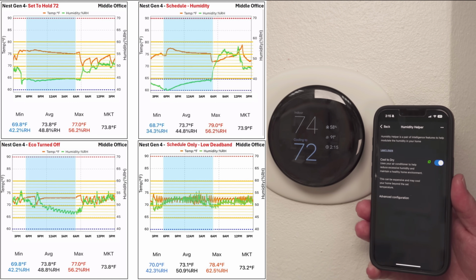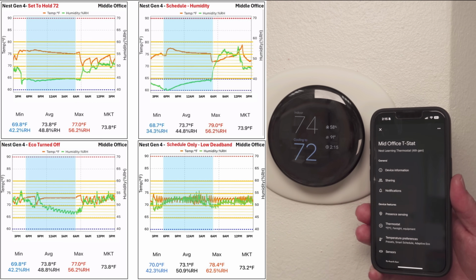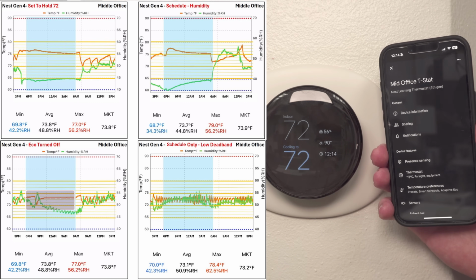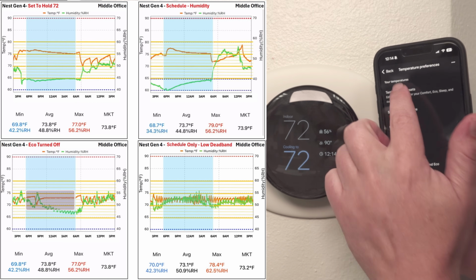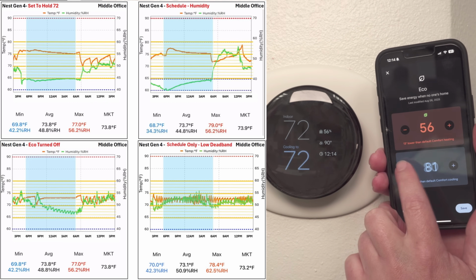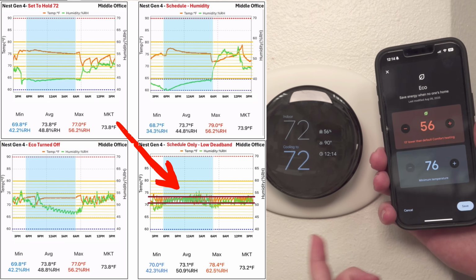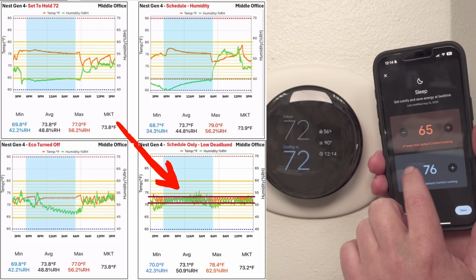Since this is the middle office and it only has one exterior wall, it has the smallest heat load of all three zones, which is partially why we don't see it cycling much at night. To fix this, I changed the temperature swing settings to 2 degrees, and now it runs all night, which is way more ideal for comfort.